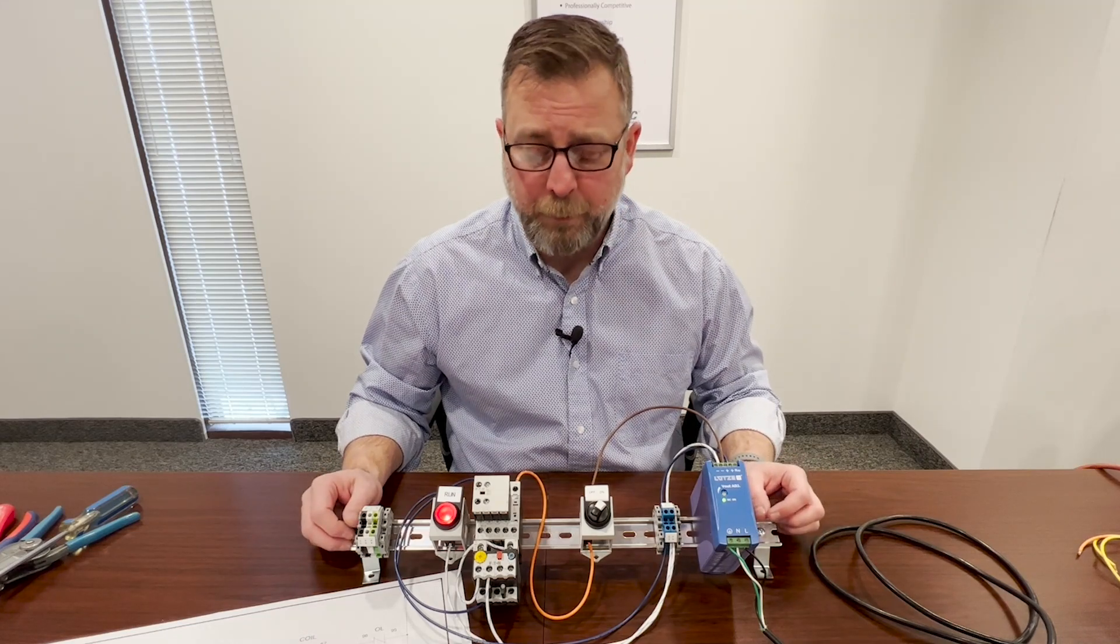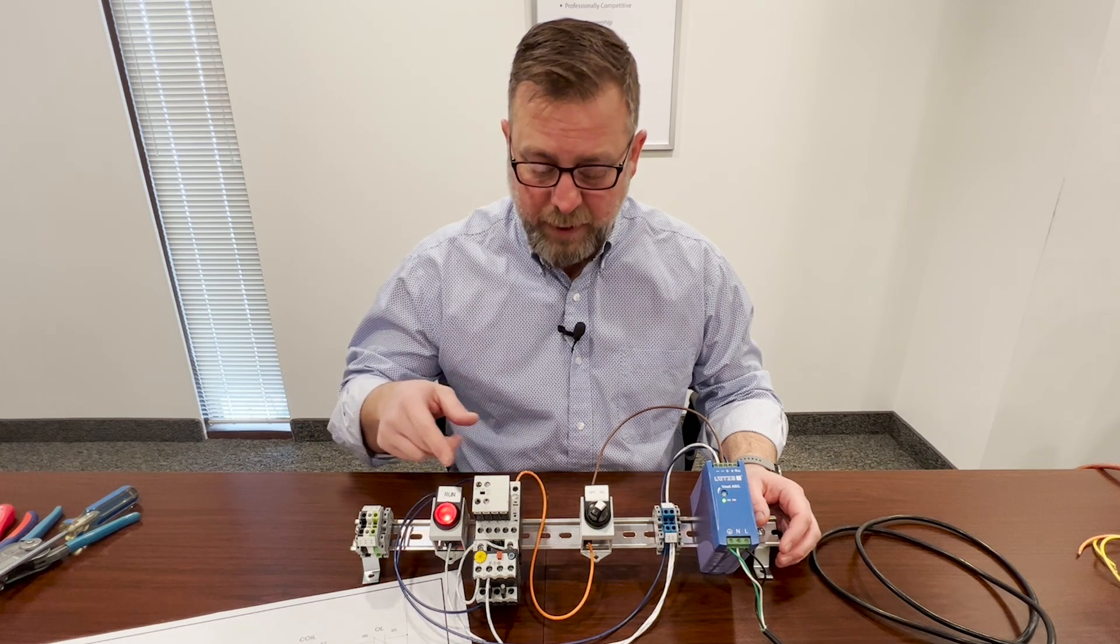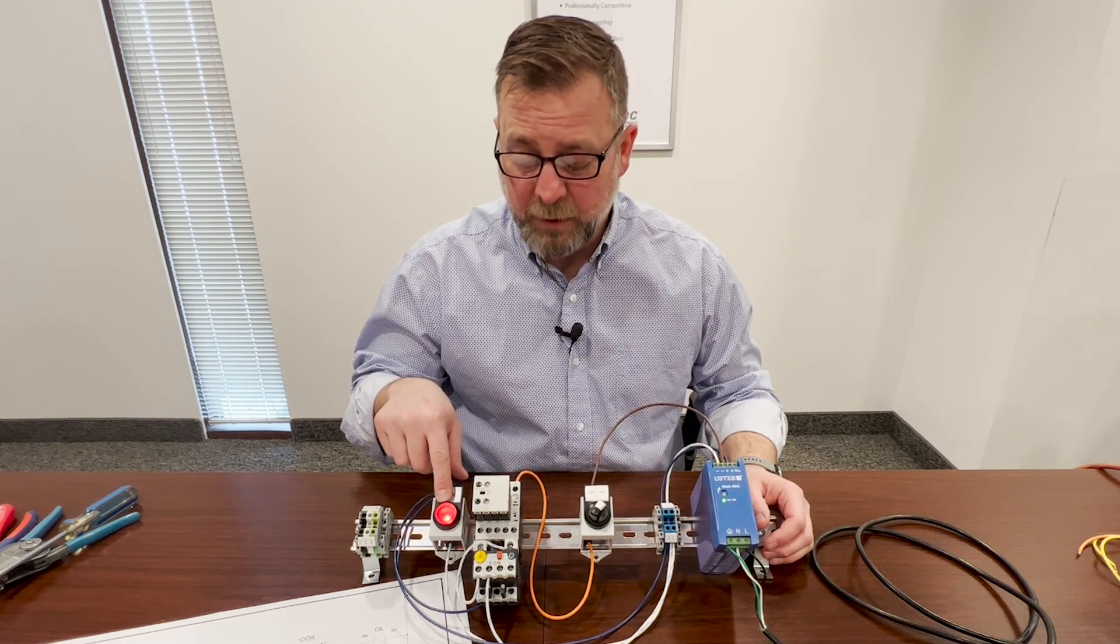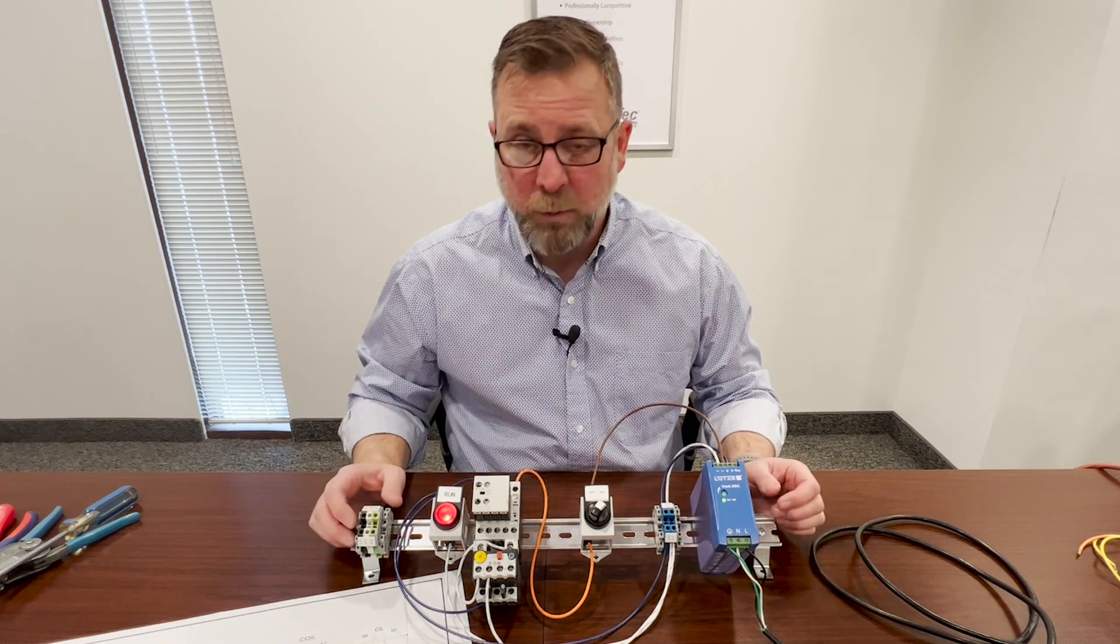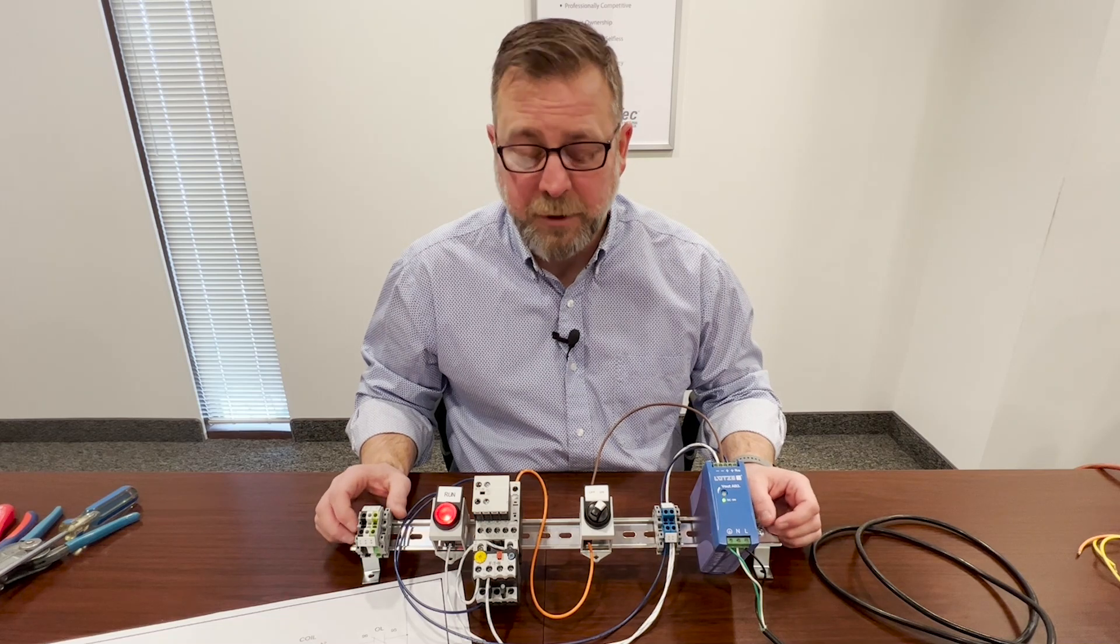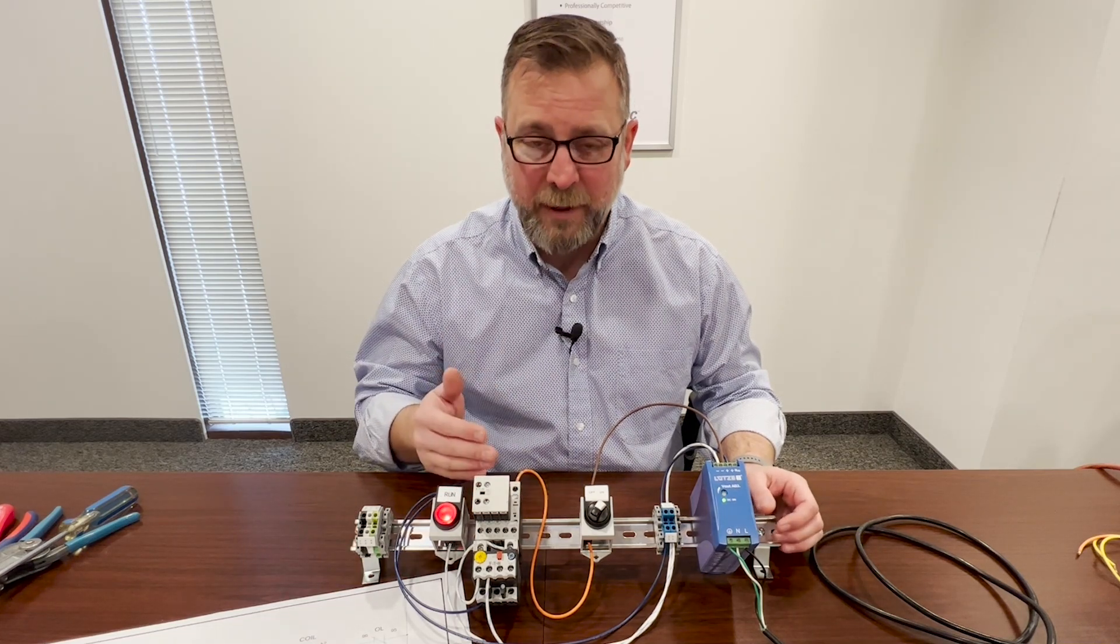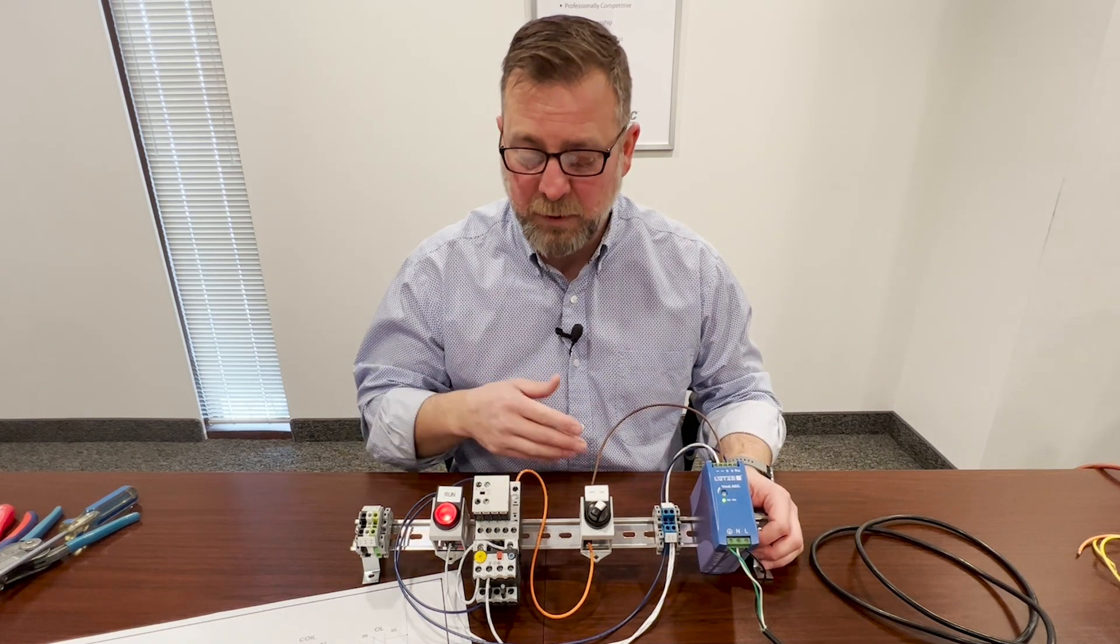This is the problem with two-wire control. If I lose power, when the power comes back on because the switch is on, the light bulb is going to turn on. The motor starter is going to turn on automatically. So you have to make sure that two-wire control is actually right for your application. You might not want this starter to turn on right away when power comes back on. You might want to have to tell it to start as opposed to it automatically happening.